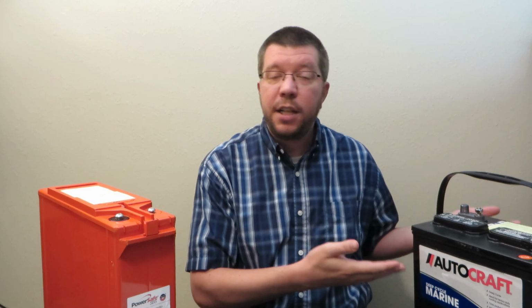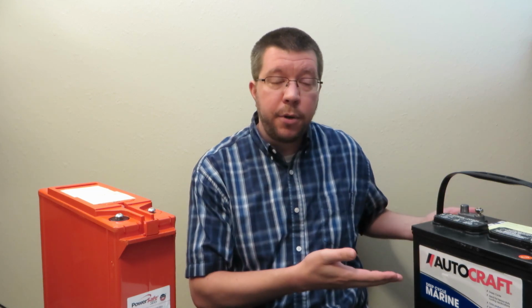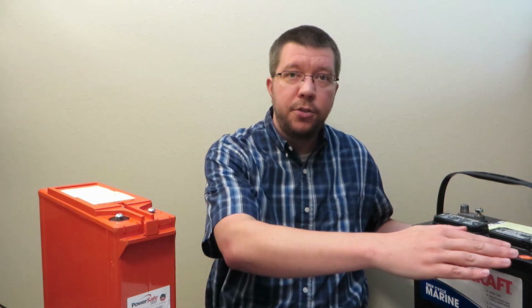There are gel batteries, which is essentially a flooded battery with a gelling additive added to the electrolyte. This helps with acid stratification and some other things. It's not very commonly used anymore, so I won't cover that. Flooded valve-regulated lead acid hybrid batteries, which is essentially a flooded battery with its construction where the vents are sealed, so you can't service them, and they're specially designed so that they use less water and retain that water longer. And then there are traditional flooded batteries. Those are the primary constructions, and within each of those there are other chemistries.